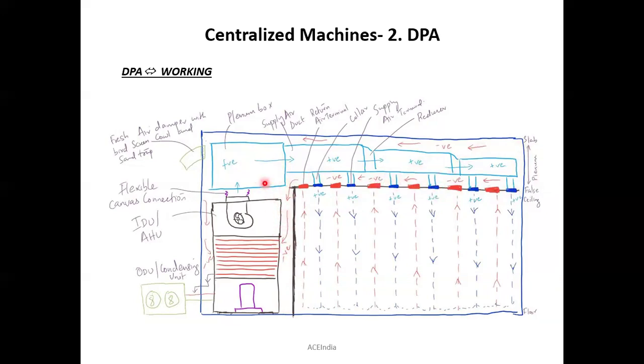At the same time, on these DPA rooms, they will be provided the fresh air damper. That means the fresh air duct. So the atmospheric air should enter right inside the DPA room, and thereby the return air and the fresh air should be properly mixed on the backside of this machine. Backside, which means the return air grill or the return air side. On the inside of the structure, you can see the air filters will be there. And again, the evaporator, sorry, both the return air and fresh air should again get in contact with the evaporator coil and again be pumped back to the same supply line itself. So this is how the DPA should operate.